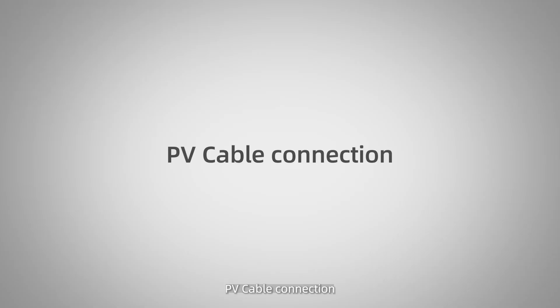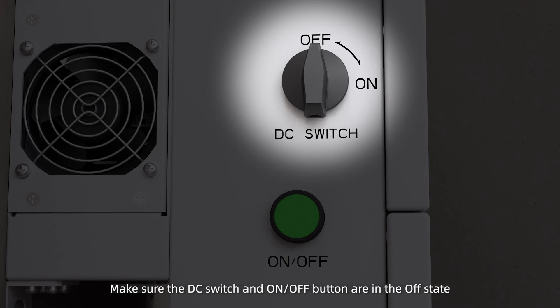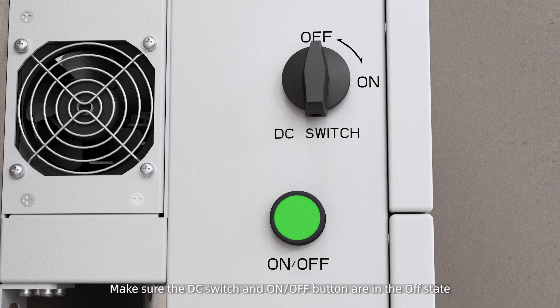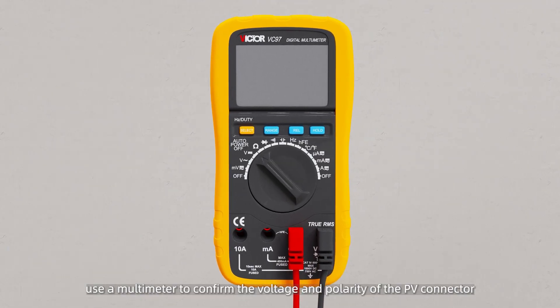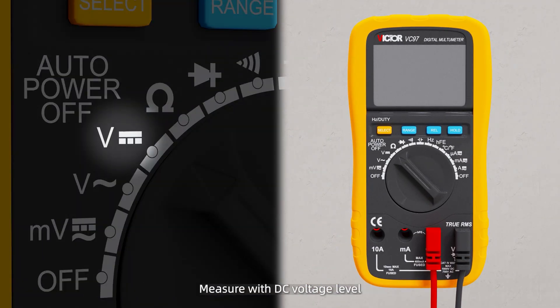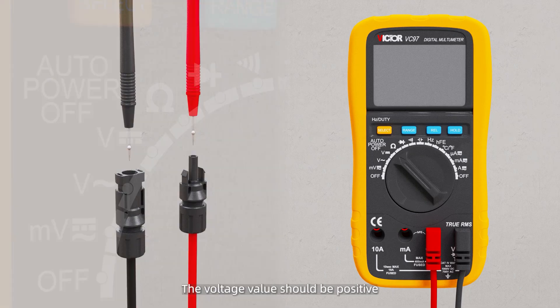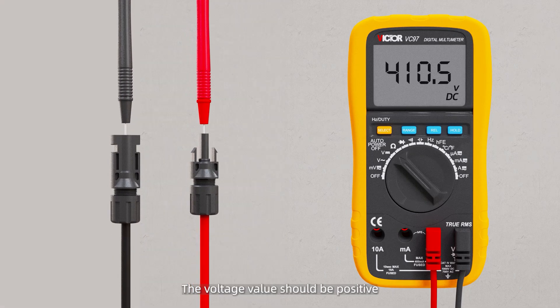PV side connection. Make sure the DC switch and on-off button are in the off state. Use a multimeter to confirm the voltage and polarity of the PV connector. Measure with DC voltage level. The voltage value should be positive and within the allowable range of the inverter.